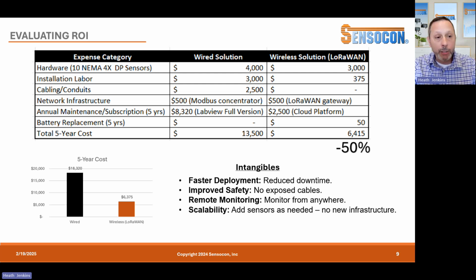Hardware, that initial cost - let's use 10 NEMA 4X weatherproof differential pressure transmitters. Doing a search and using a rough average for the wired solution, I came up with $4,000. The wireless solution was about $3,000. We can bite around the edges of that, but generally speaking, the hardware cost is going to be about the same - it's more or less a wash.